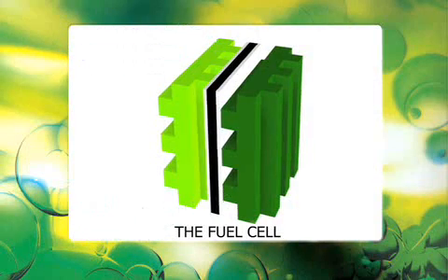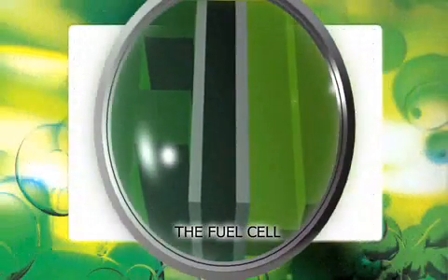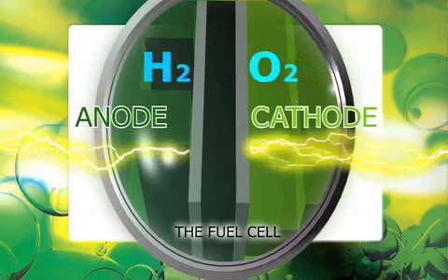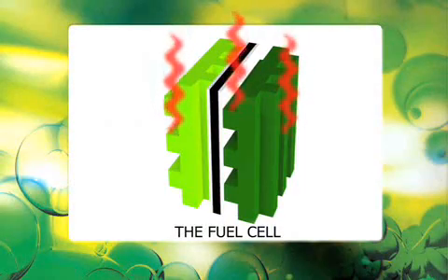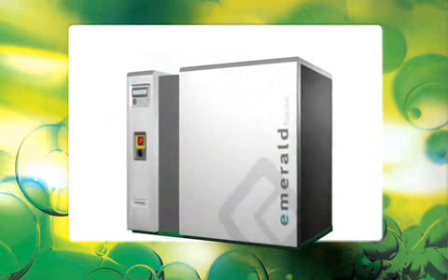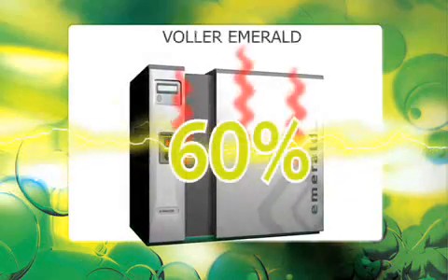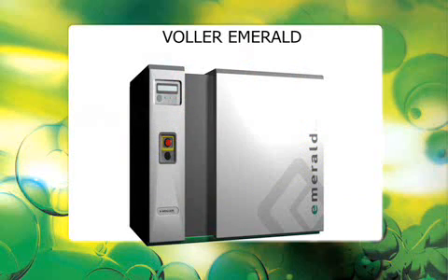The reaction takes place on the fuel cell's special membrane — a thin, flexible film coated on both sides with a catalyst layer. One side is the anode and the other is the cathode. When hydrogen is fed to one side and oxygen to the other, electricity is created, as well as a small amount of water. An important byproduct of this electrochemical process is heat. As a result, the fuel cell creates electricity for recharging batteries and heat which can be used to replace or complement water and room heating. Pure electrical efficiency of 25 percent and combined power and heat efficiencies of more than 60 percent make the Voller Emerald fuel cell a truly portable and powerful alternative to the traditional generator.